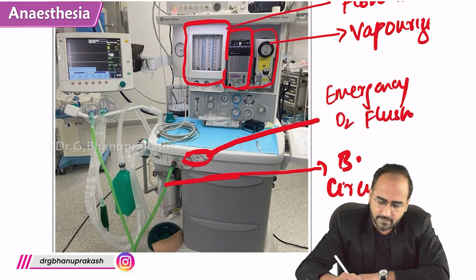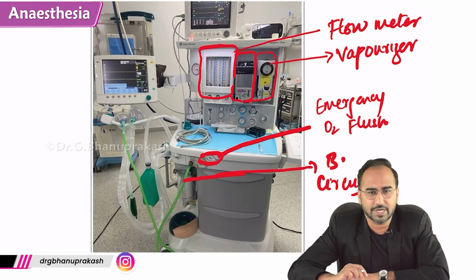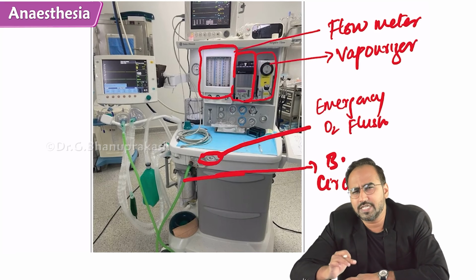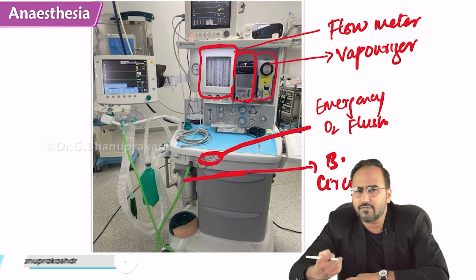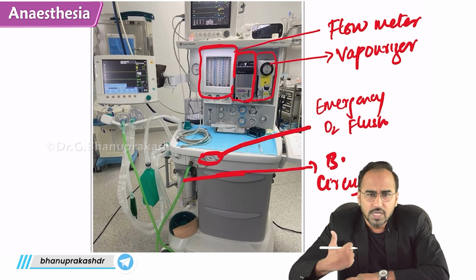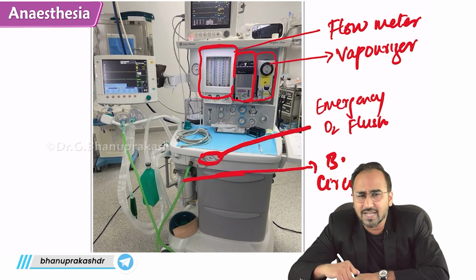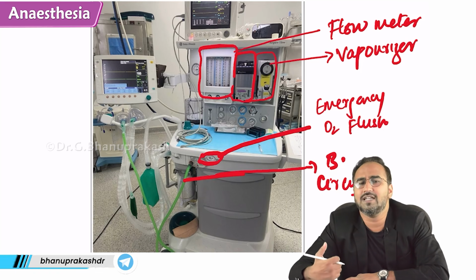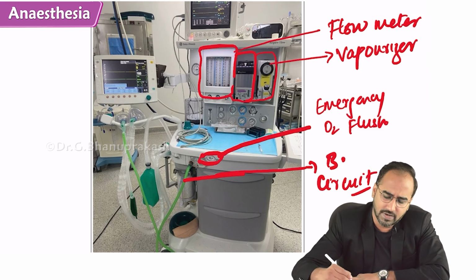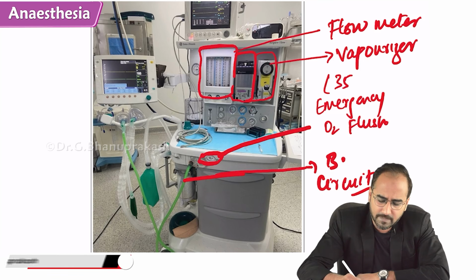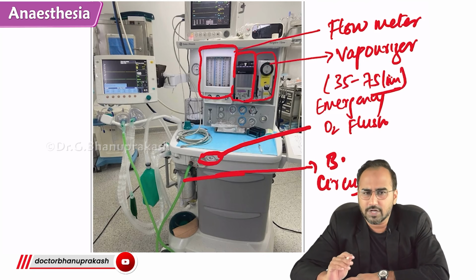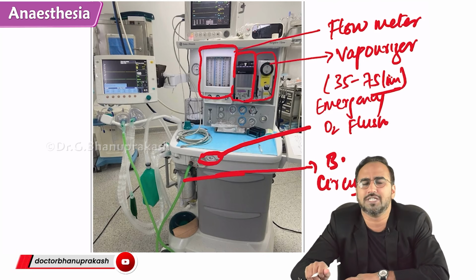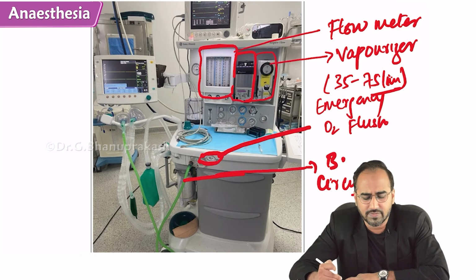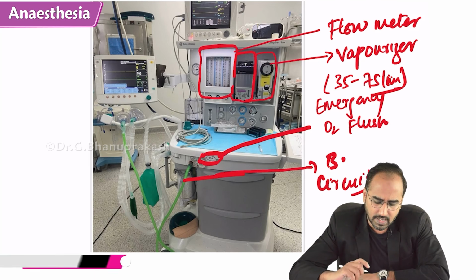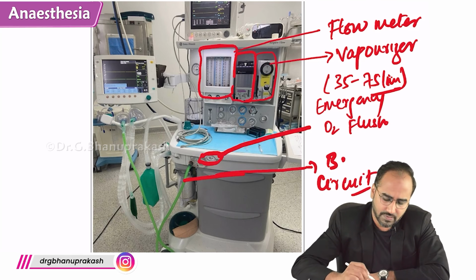Emergency oxygen flush. What is the function of the emergency oxygen flush? Imagine during anesthesia, your patient desaturates. There is a fall in oxygen saturation. What will you do? You will push this button, and it will deliver oxygen at a tremendous rate. What rate are we talking about? 35 to 75 liters per minute. If the patient develops sudden hypoxia, you can just push this button and deliver oxygen at 35 to 75 liters per minute. So that is the emergency oxygen flush.